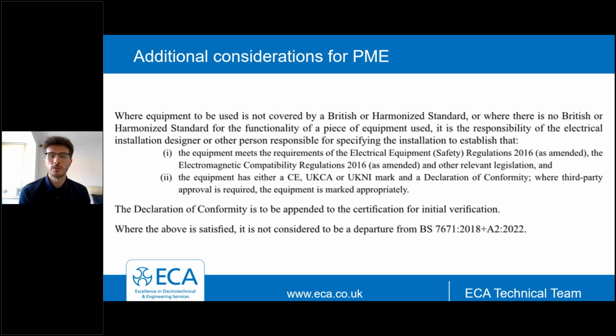Where the above is satisfied, this is then not considered a departure from BS 7671. So the reason I focus on this point so heavily is that feedback we're getting from out in industry, from maybe assessors that are carrying out the early assessments, is that some installers are selecting suitable equipment to meet the requirements of this regulation that meet indent 5 with the open PEN device. However, they are failing to provide or obtain this information from the manufacturer and then provide it to the client with the certification as part of the initial verification and handover process.